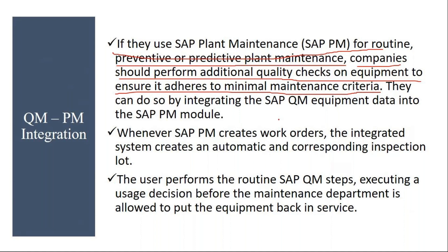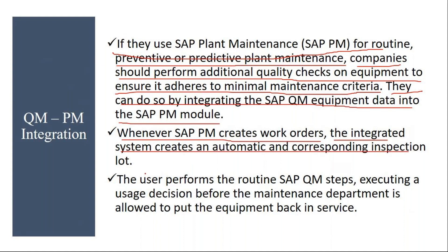They periodically calibrate the equipment in the quality control lab just to ensure that equipment is functioning properly. They can do so by integrating SAP QM equipment data into the SAP PM module. Whenever SAP PM creates work orders, the integrated system creates an automatic corresponding inspection. In the PM module, when they create a calibration order, it will automatically generate an inspection.